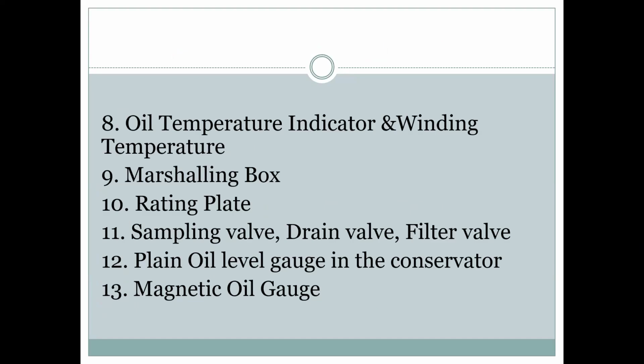Next, oil temperature indicator and winding temperature indicator. The oil temperature indicator and winding temperature indicator normally have two contacts. When the temperature goes up suddenly, the control room gets the signal that the temperature is going up.